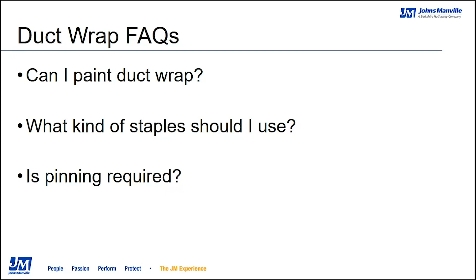And one of the things that we want to make sure that you know is when you do pin on the underside, it does compress that insulation, so it does take away your insulating power, but it also compromises your vapor barrier. So as that hole is punctured through with that mechanical fastener, you want to make sure that your contractor goes back and at least tapes over that with the proper tape to seal that hole up and make sure that it keeps your vapor barrier intact. So pinning is a common practice, especially on large ducts. We do approve it. It is fine to do, but just make sure that you're using some of those common steps when you have that application.